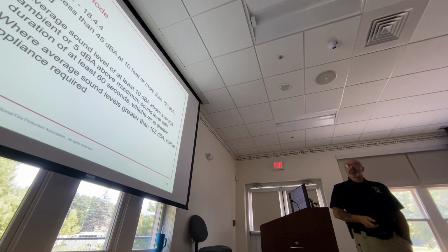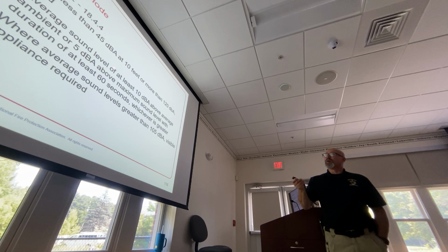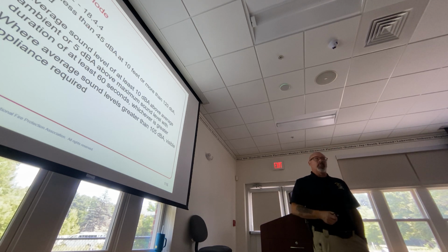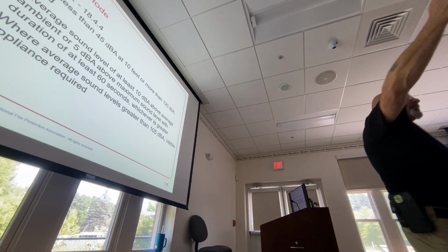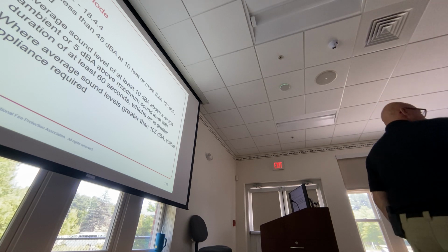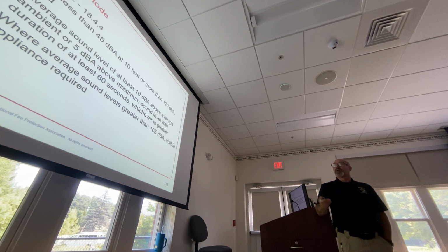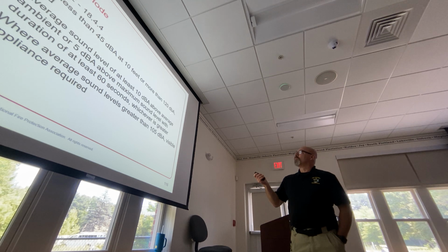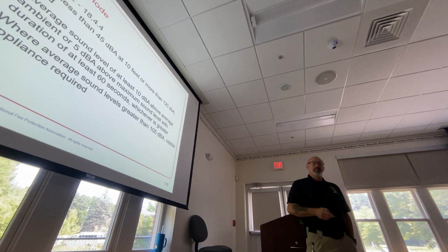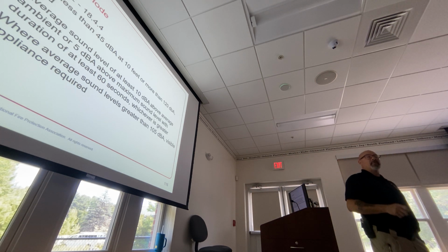When they're talking about 10 feet or more, it has to be not less than 45 decibels if I'm 10 feet away from that notification device. Okay, it's the distance you are away from that alarm that has to be 45 decibels, but not more than 120 decibels. So you don't want it too loud.